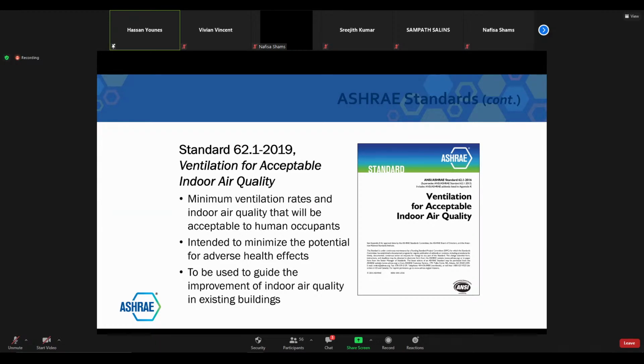The third way to be compliant with the standard is called the indoor air quality procedure, and that basically is a mass balance equation. You start by assuming the type of pollutants being emitted inside a particular space, and then you do a mass balance and see how much outside air you need inside that room to dilute the pollutants to a certain level. Now, this is not widely used because it takes more time and needs more experience, and it's generally not acceptable in the UAE. So in the UAE we mainly use the ventilation rate procedure, which basically tells you the amount of outside air that is required based on the number of people and the area of spaces.